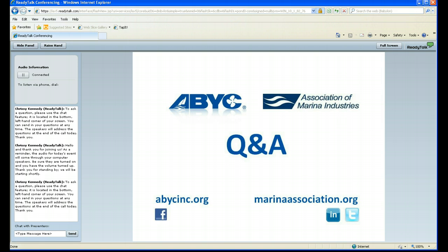To answer your question, I've done both, and me being a deputy electrical inspector myself, I would accept the ground fault monitoring with a shunt trip breaker, because there are very little options out there, especially if you want to put the ground fault monitoring or the ground fault protection on the main.